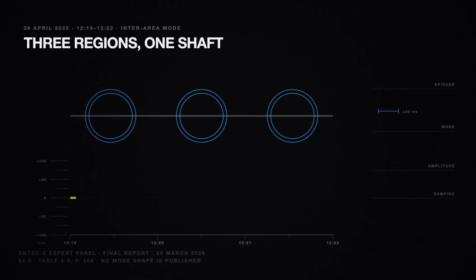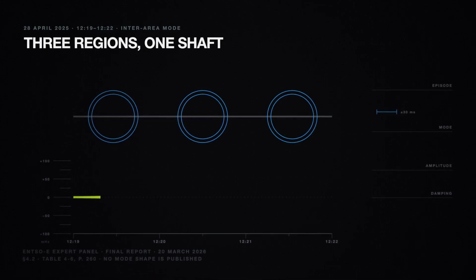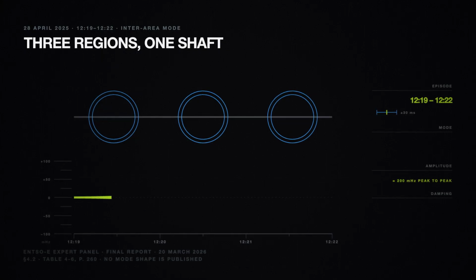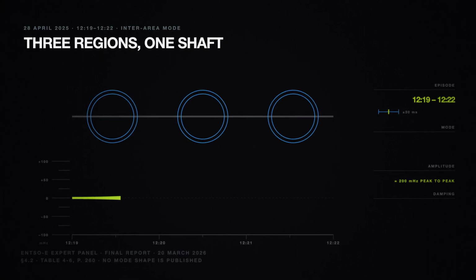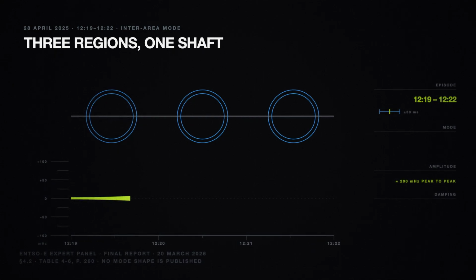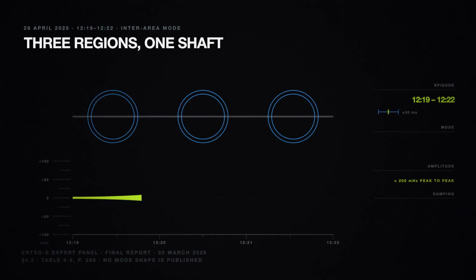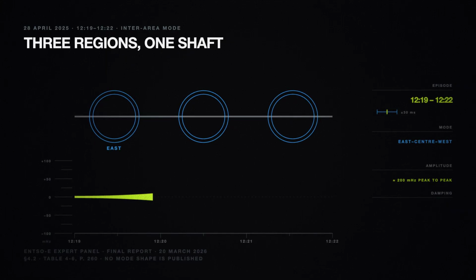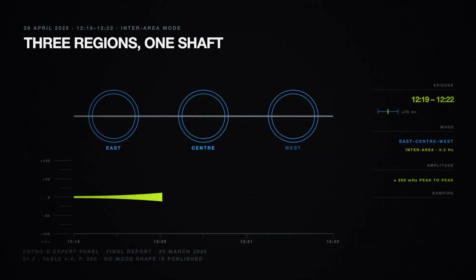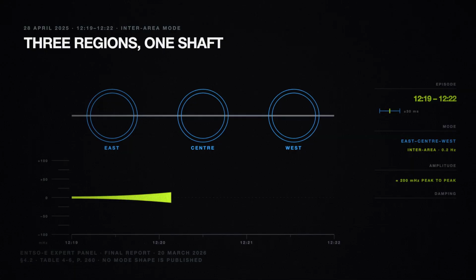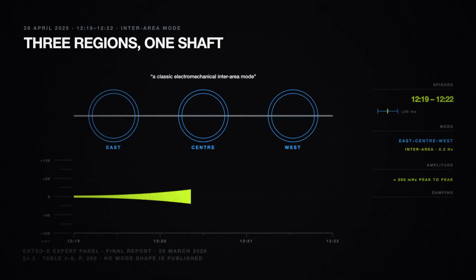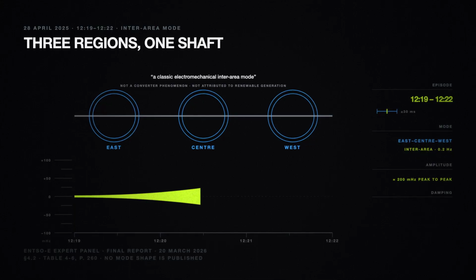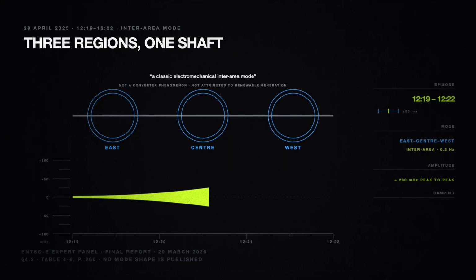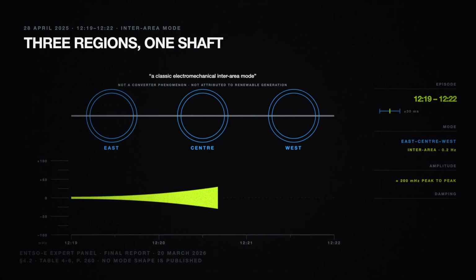12:19. The southwest corner of continental Europe began swinging at 1/5 of a hertz. It ran for 3 minutes, until 12:22, and it reached about 200 millihertz. Twice the amplitude of the episode 16 minutes earlier, and a completely different object. The panel names this one, the East-Center-West Inter-Area mode, at 0.2 Hz, one of the 2 frequencies the modal survey had already found. The report describes it as a classic electromechanical inter-area mode. It is not a converter phenomenon, and no part of the document attributes it to renewable generation.